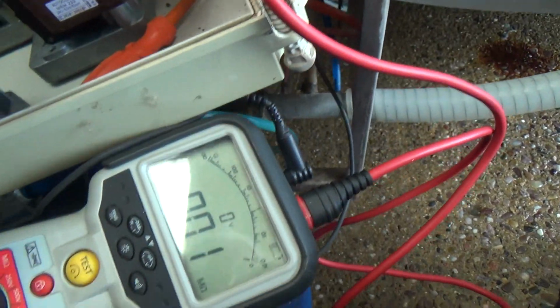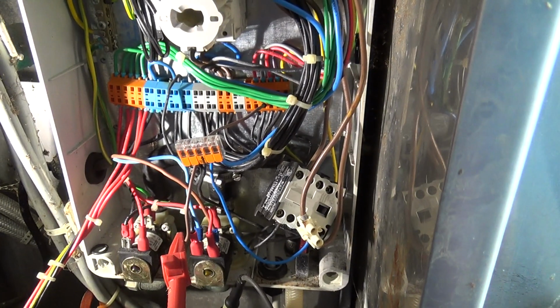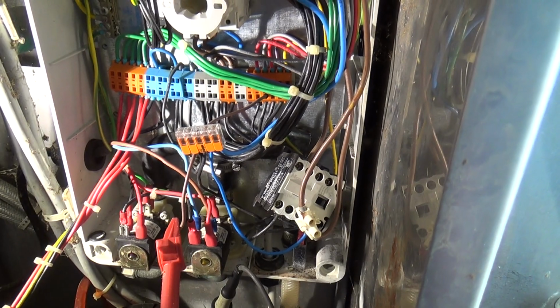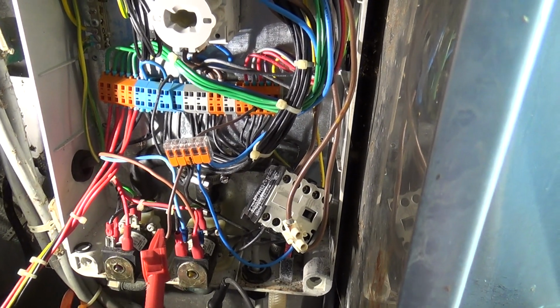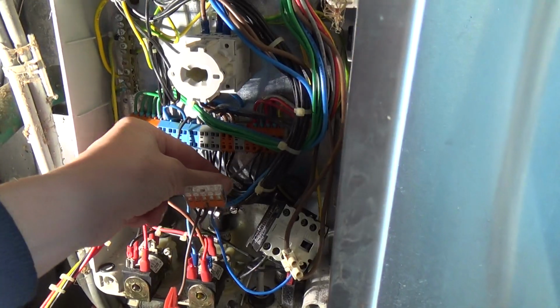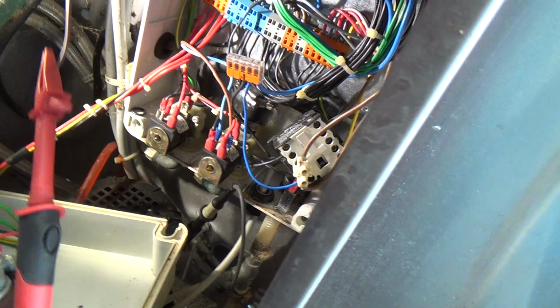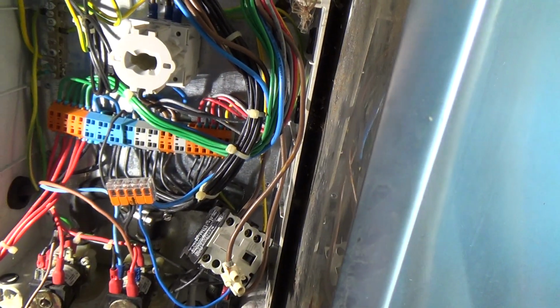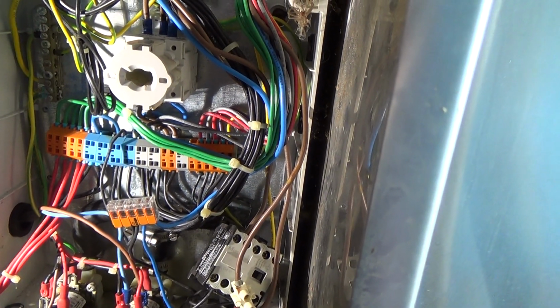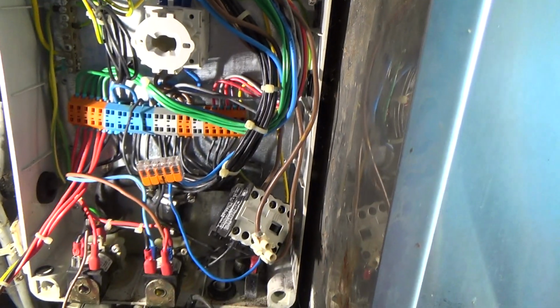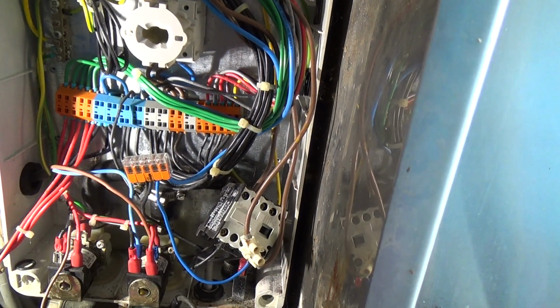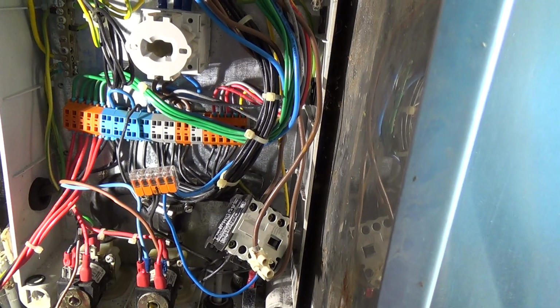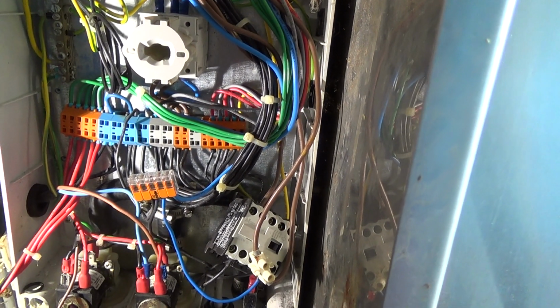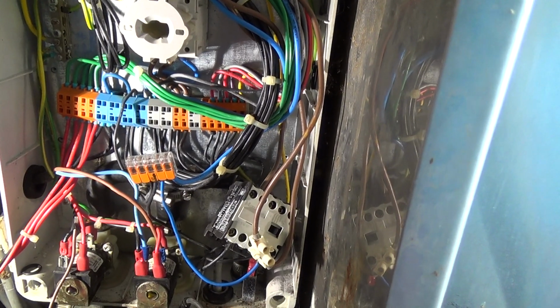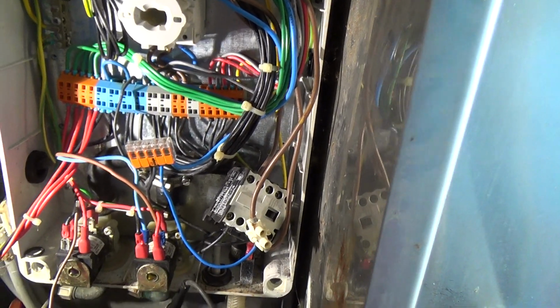Okay, we've got a dead short on that grey wire. We'll have to trace where that goes. That may well be the booster pump. Couldn't get the thing in there, so I'm using a little wire as an extender. So that grey wire is faulty. So we've got the red, purple and yellow to test, and then that's pretty much it. Well, yeah, we've got something on that grey, so that may well be the booster pump, which may not be actually faulty. It might just be going up the neutral.